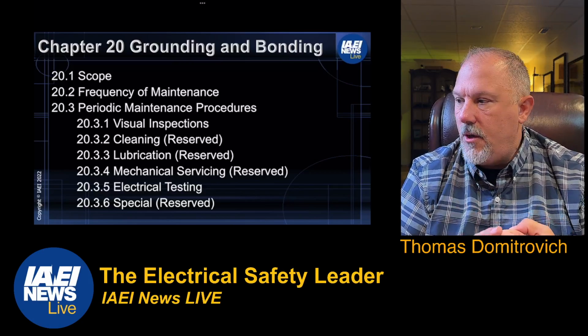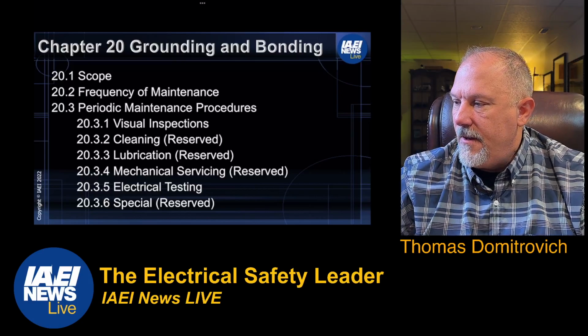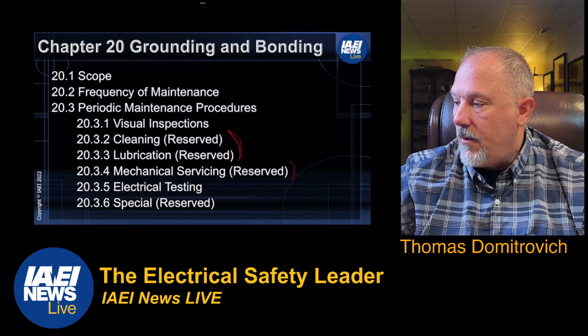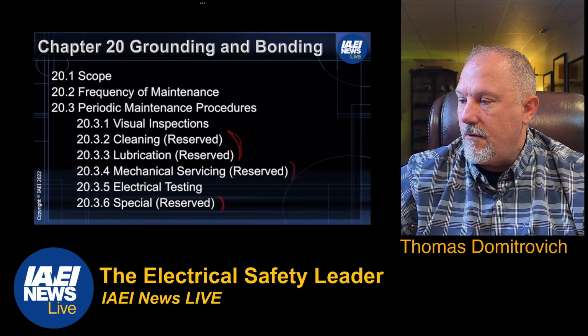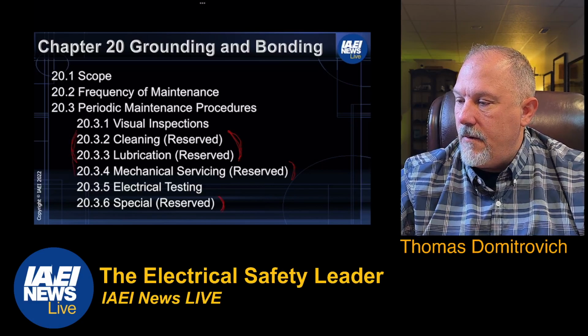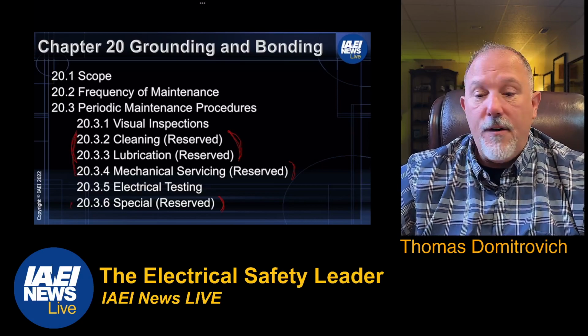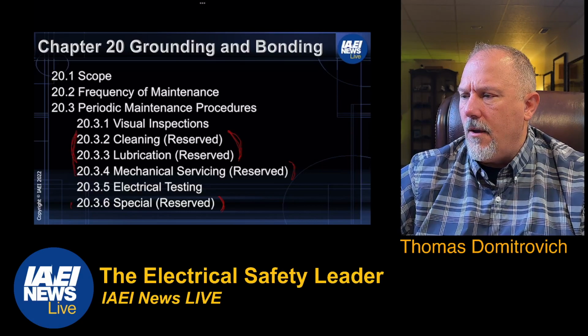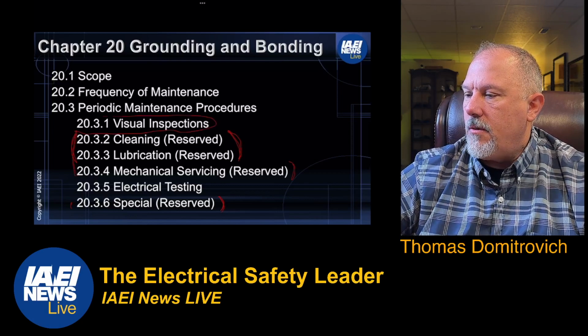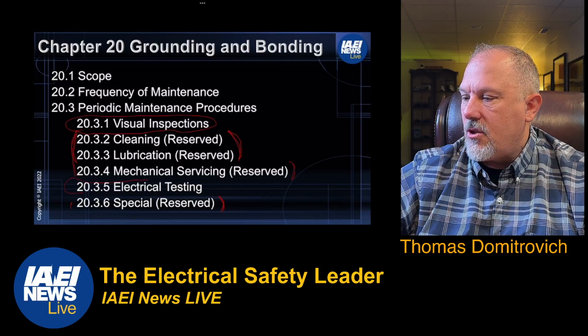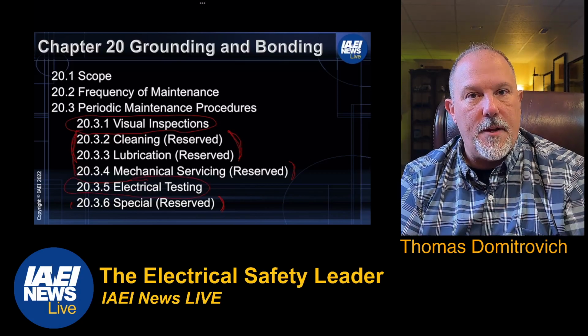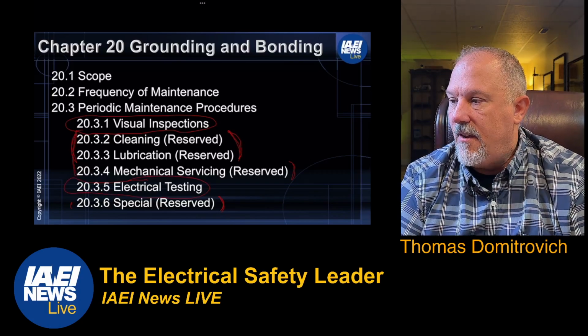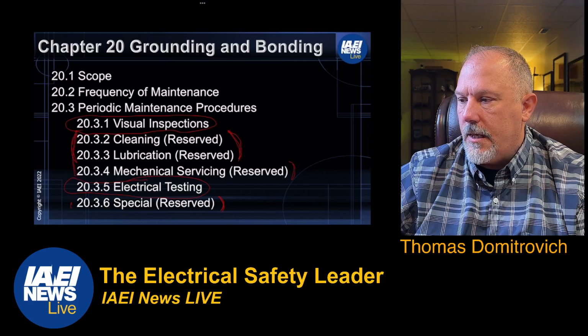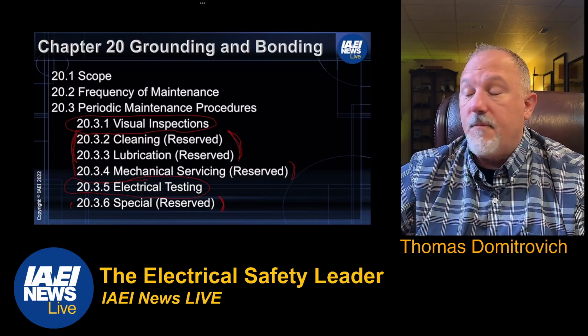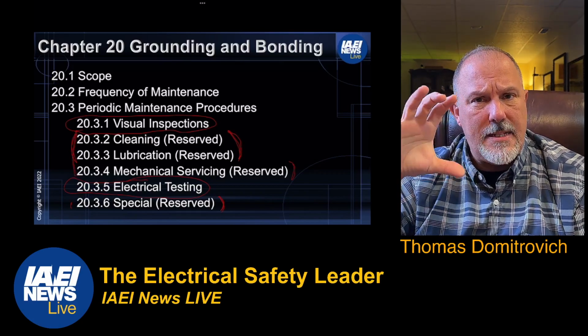Now in the periodic maintenance section, you'll notice a couple of these subsections are reserved. So out of the three sections here, out of all the requirements in 20.3, we're only focused on visual inspections and electrical testing. So we're going to visually inspect the grounding and bonding, and then do any electrical testing from a periodic maintenance perspective. Cleaning and lubrication are reserved, there's no content there, but we kept them reserved because this is sort of the structure maintained across each of the chapters.